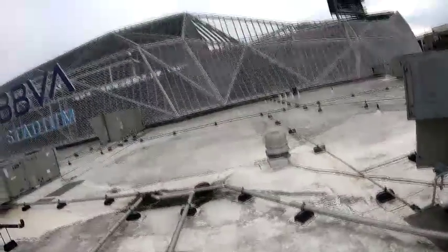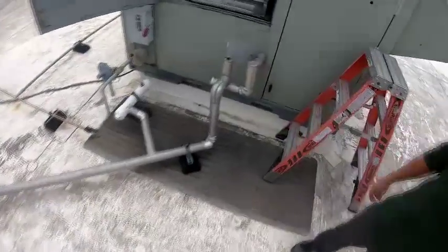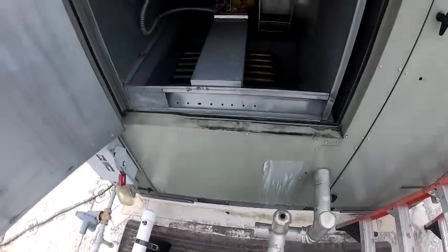Well, I tell you what, we spent hours trying to get that out. We put the pulley on to try to pull it out. That was a pain in the butt. Is it a condenser fan motor or the blower motor? It's a blower motor. And this one here is blowing the fuses, huh? Yeah, it blew out lines 2 and 3.